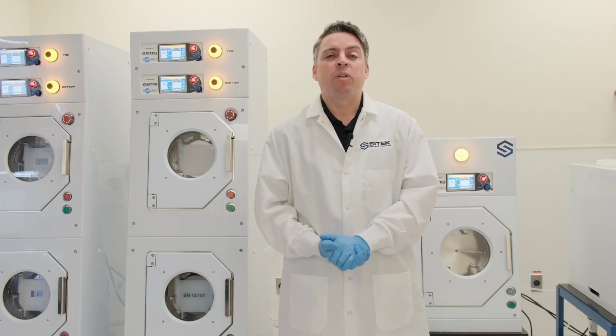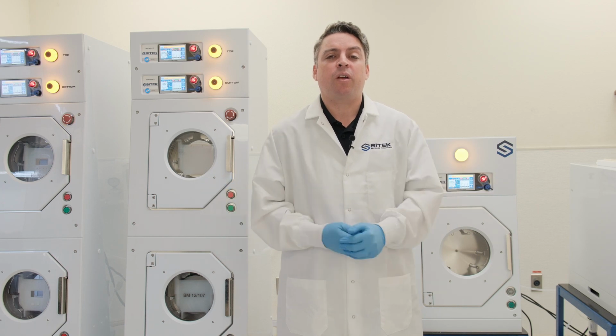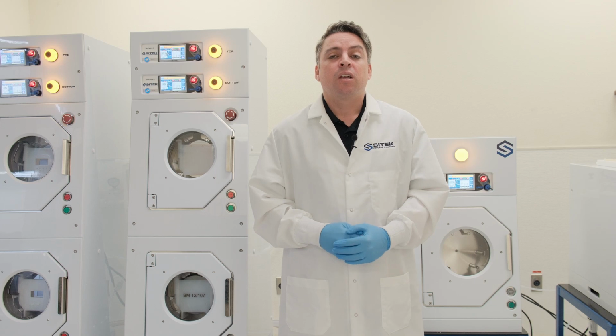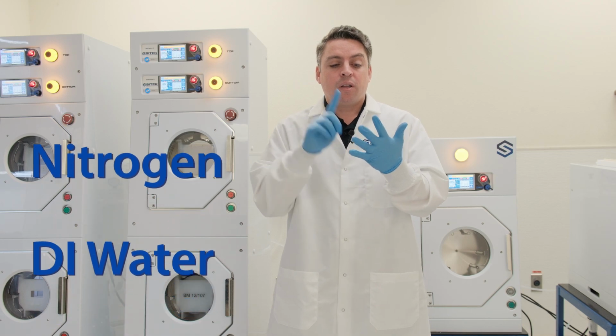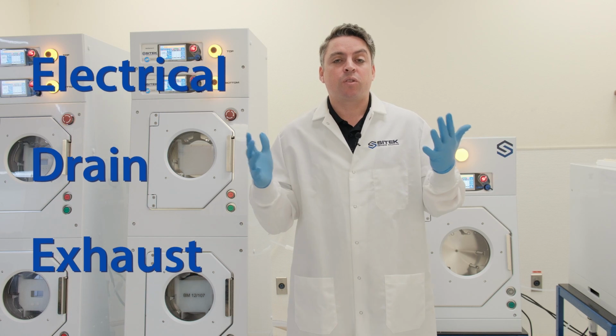Hello, my name is Daniel Mullany from SITEK Process Solutions, and today I'm filming a short instructional video on how to successfully set up your spin rinse dryer with regards to facilities. So on the SRD there are 5 total facilities, which includes nitrogen, DI water, electrical, drain, and exhaust. And so I'm going to cover those quickly.